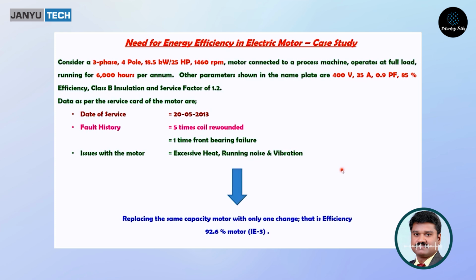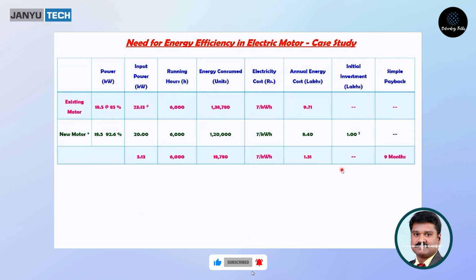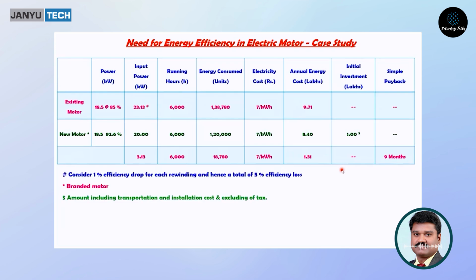So an IE3 motor of the same capacity has an efficiency of 92.6%, right? Now you put a table. Existing motor is 18.5 kilowatt, 85% efficiency. You are requested to reduce the efficiency by 1%, because we know that each time a coil is rewound, 2 to 3% is the loss. But we are taking only 1%. So 5 times rewound, so 5% loss.